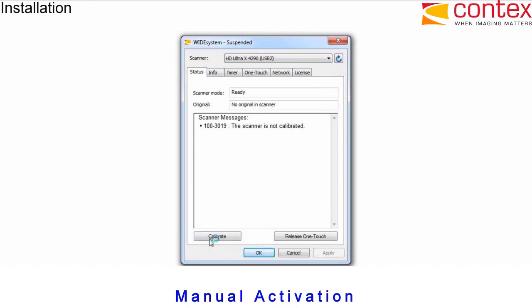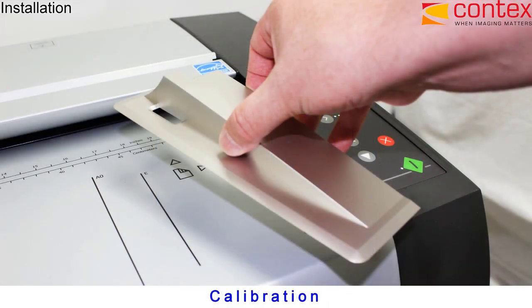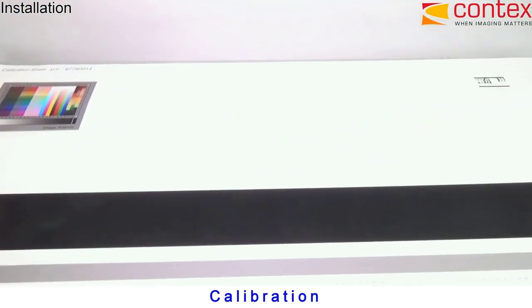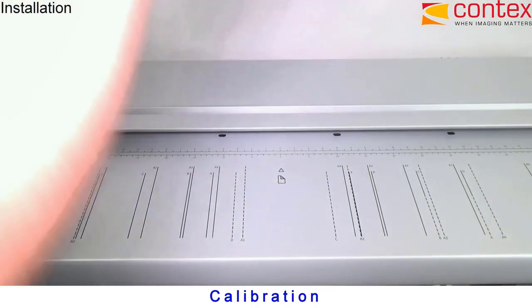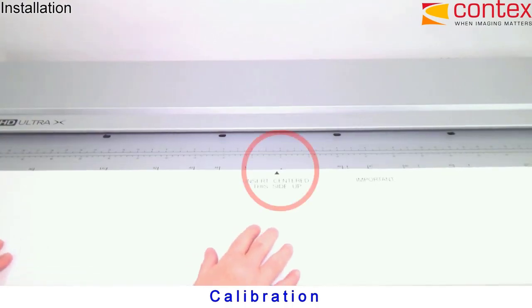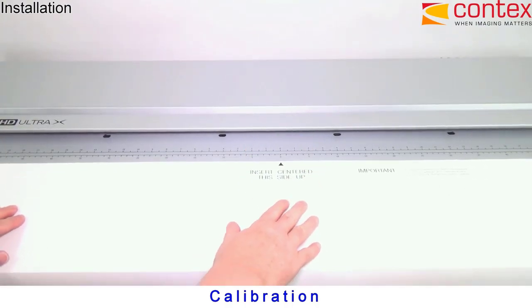and calibrate the scanner if asked to do so. Before inserting the calibration sheet, it is necessary to remove both of the magnetic paper guides, if they are fitted, so the sheet can fit into the scanner. Insert the calibration sheet centrally into the scanner with the image face down. Making sure the arrows line up.